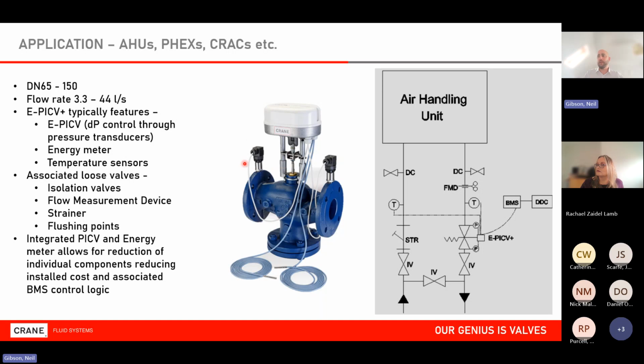So the previous example I showed was the larger flanged smart valve. So again, we've got pressure sensors here, but we've also got our temperature sensors. And again, we just locate those into the flow and return of the pipework. And I can do the same thing, the separate Modbus registers, where I can set my return temperature limit. I can set my delta T. I can set my power. I can monitor my power, which means that in this example on an air handling unit where I may have traditionally had a flow meter, a heat meter with its temperature sensors, I no longer need that now. I can get rid of it. It's all built within this.